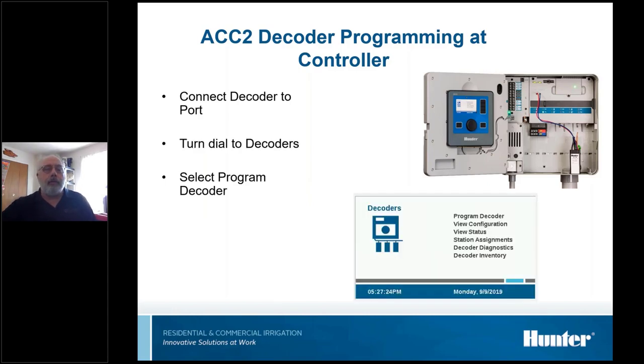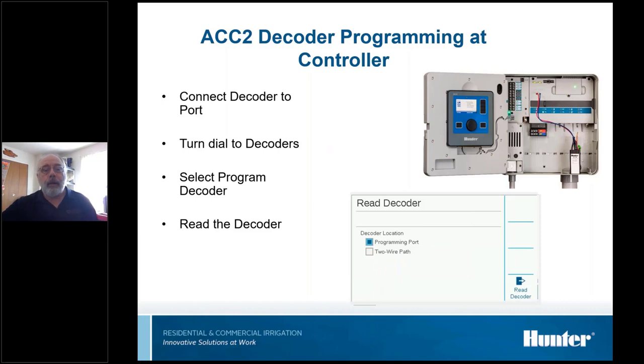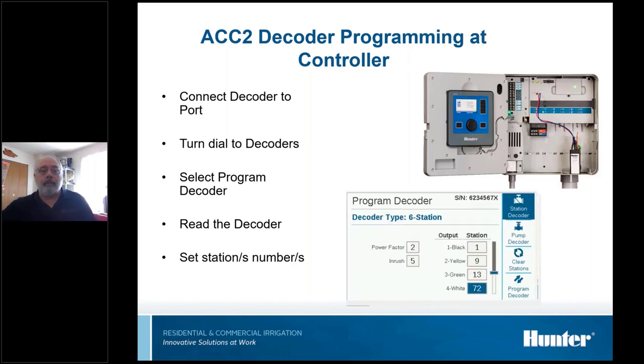Connect the decoder to the port. You're just on the dial. We're going to go to the decoder screen. We're going to select program a decoder. Then we're going to need to read the decoder. And in this case, we're going to read it from the programming port. It has the ability to read decoders out in the field, but that's not what we're doing. We're programming it, so we're going to read what's in the programming port. When you do, it'll bring up and tell you everything it knows about that decoder. In this case, it's a 6-station decoder.